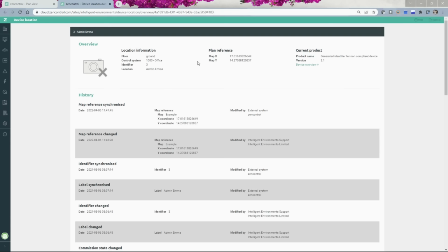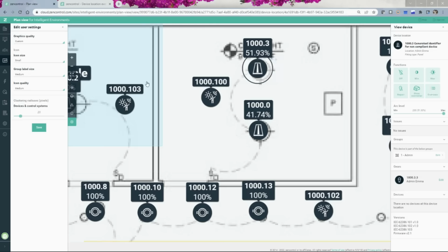If we had an emergency fitting here, it's going to tell us at a glance how many times the battery's been discharged and what its state was. Did it, when it did its reporting, did it meet the 90-minute criteria? Did it only get to 70 minutes? All of that history is held in that overview tab. So every time you use your Planview and open it, it's maintaining the information live. So you can pull down and grab it out each time as you need it.